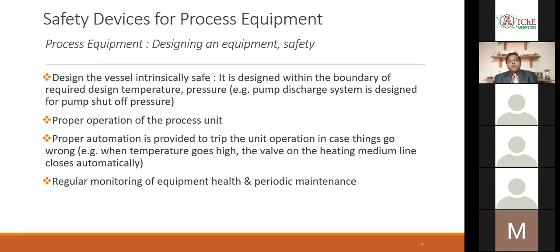and again put it back. For the other big equipment like, say, distillation column and all, we do an external health check by, say, radiation check to check if the thickness of the vessel is as per the specified standard or not. This is also very important because if there is something wrong, we need to be alarmed previously rather than waiting for a catastrophe to happen.